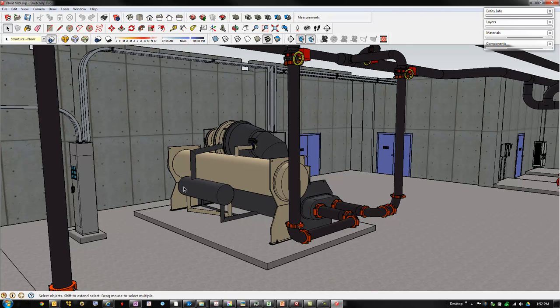It's called an economizer. It's different from the economizer in an air handling system, but it's an economizer for a chiller. And the idea is, if you know a little bit about refrigeration, you're working with a saturated fluid in different phases, and you evaporate it at a low pressure in the evaporator. In other words, it flashes from a liquid to a vapor, and the energy it takes to go from liquid to vapor is what's cooling the chilled water.